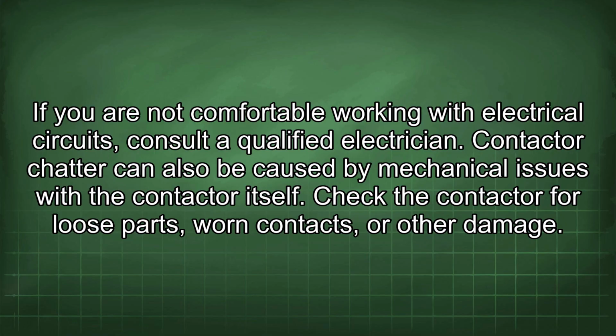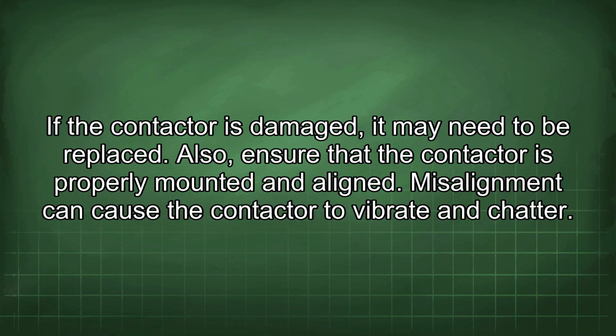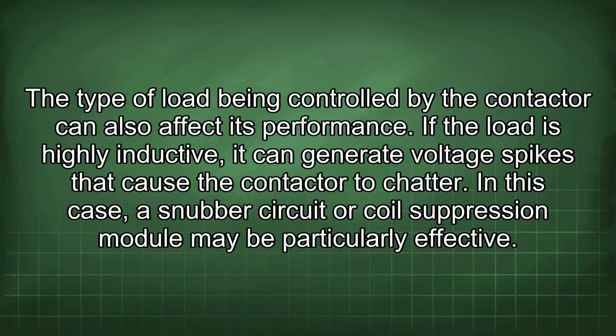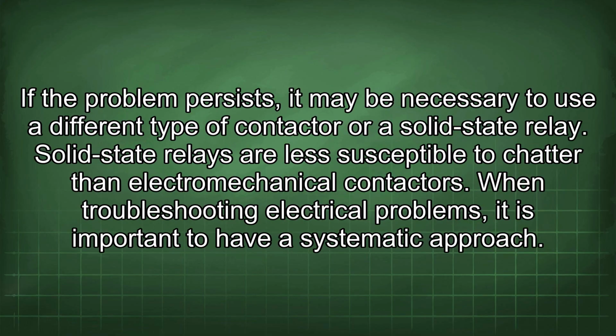Contactor chatter can also be caused by mechanical issues with the contactor itself. Check the contactor for loose parts, worn contacts, or other damage. If the contactor is damaged, it may need to be replaced. Also, ensure that the contactor is properly mounted and aligned. Misalignment can cause the contactor to vibrate and chatter. The type of load being controlled by the contactor can also affect its performance. If the load is highly inductive, it can generate voltage spikes that cause the contactor to chatter. In this case, a snubber circuit or coil suppression module may be particularly effective. If the problem persists, it may be necessary to use a different type of contactor or a solid-state relay. Solid-state relays are less susceptible to chatter than electromechanical contactors.